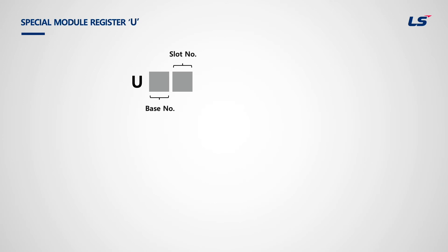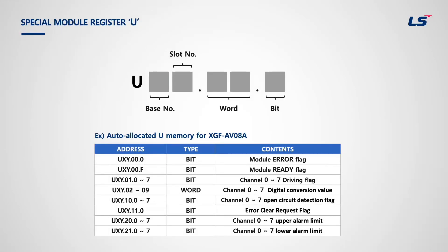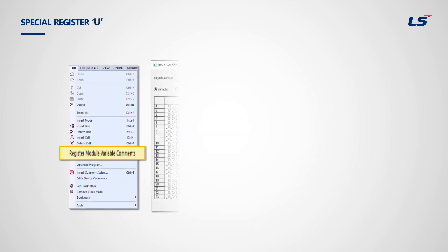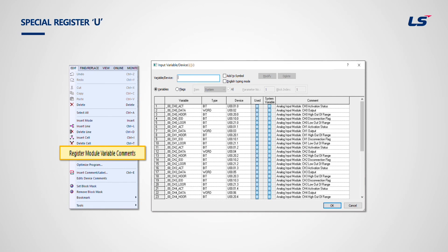U-device is a special module register. It is used to read data from special modules installed in a slot, such as analog, high-speed counter, temperature control, and positioning modules. The device address is not fixed but allocated depending on what kind of special module is used and which slot it is equipped in. The address will be registered automatically if users register module variable comments in the edit menu.